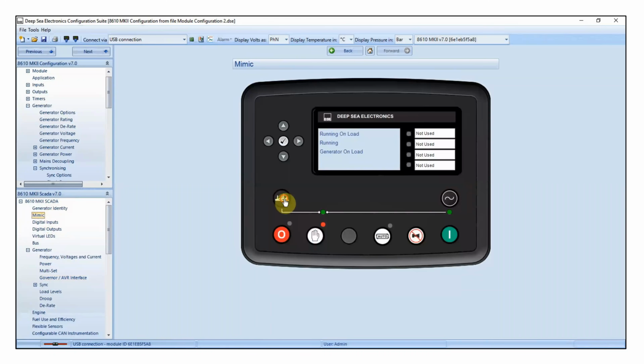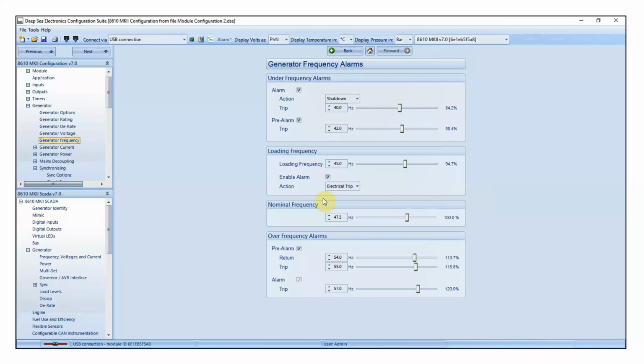But one thing many people forget to do at this point, which is extremely important, is to go back into the module's configuration and remember to change that nominal frequency back to 50 Hertz. Because every time now that we want this generator to run and close the breaker, we want it to run at 50 Hertz. If you don't make that change, every time you close the breaker, it will run at the wrong frequency. So always remember, go back, change the nominal frequency to whatever that is, in my example, 50. And that is how we set the switch 2 for the governor.